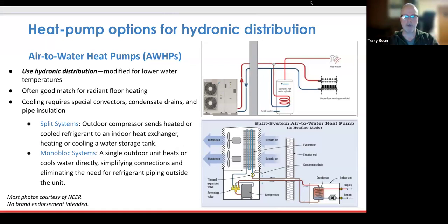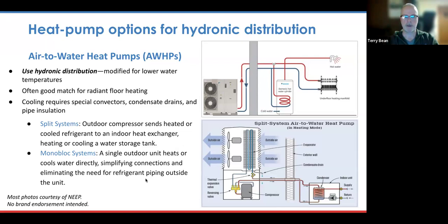So you have to think about how you are going to deal with the condensate generated by cooling. And if you're using some kind of hydronic distribution, dealing with that condensate becomes quite a challenge. So typically, there would be some sort of additional ducted cooling solution working in tandem with the hydronic heating solution, and that's still the case.